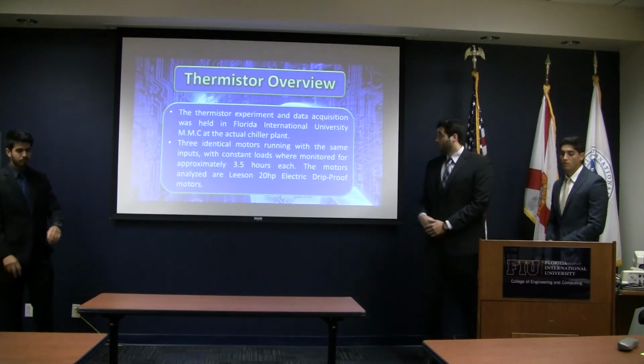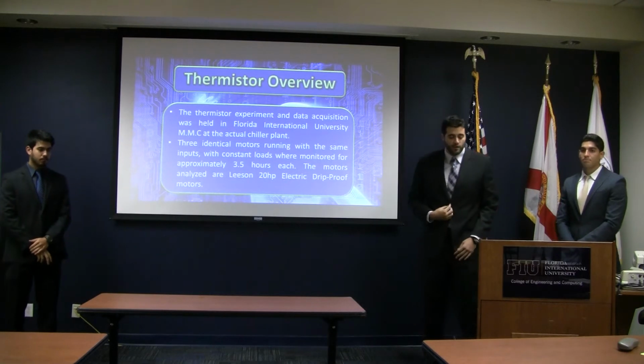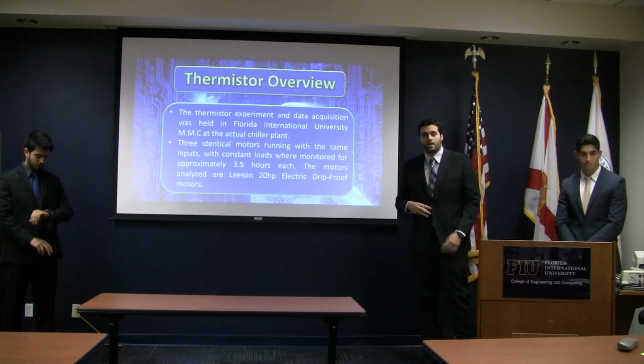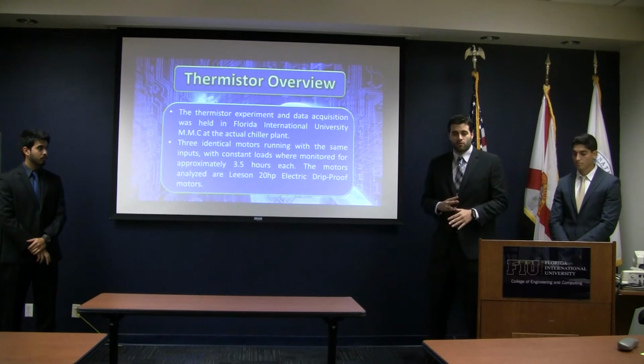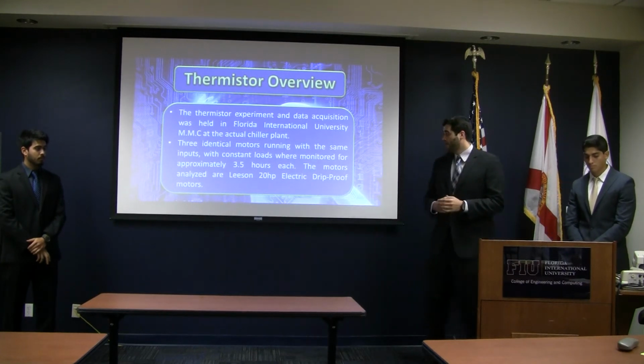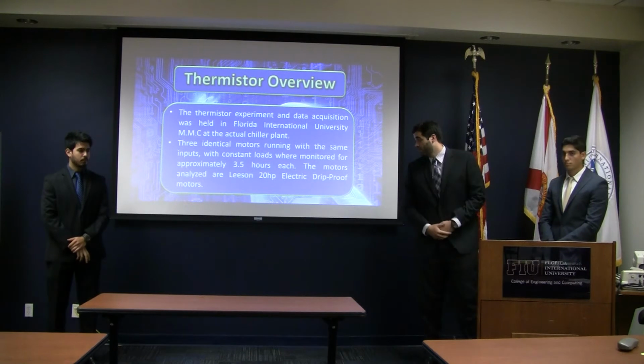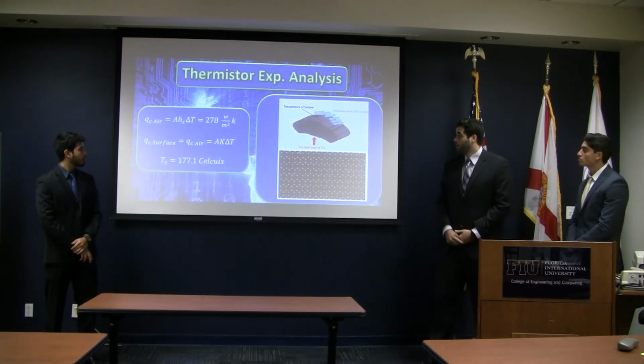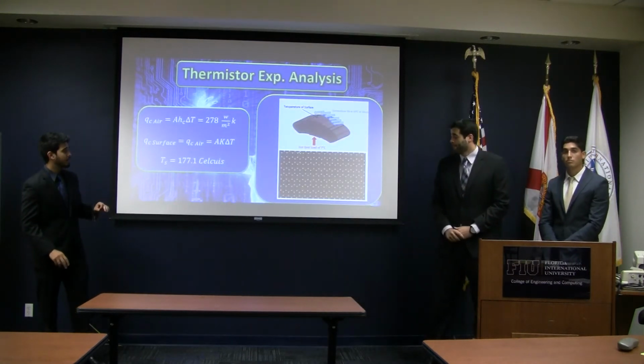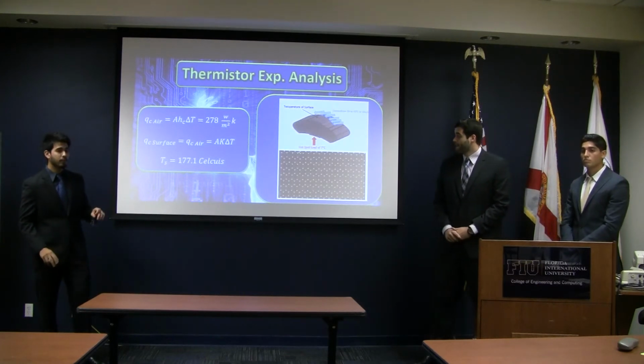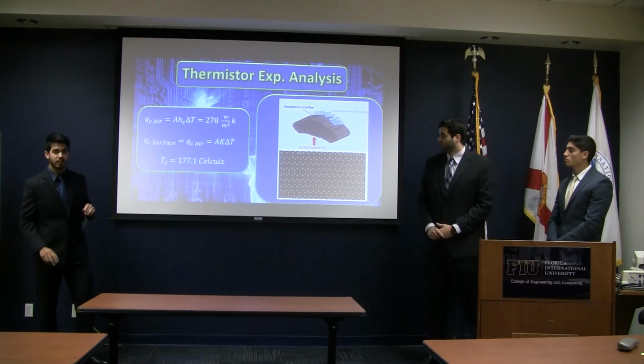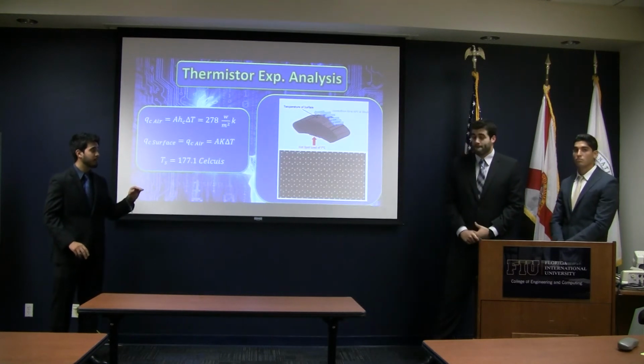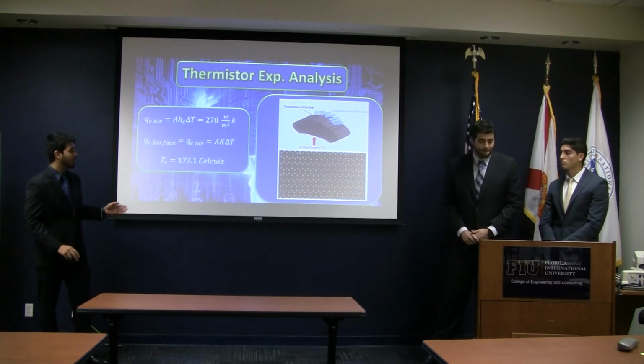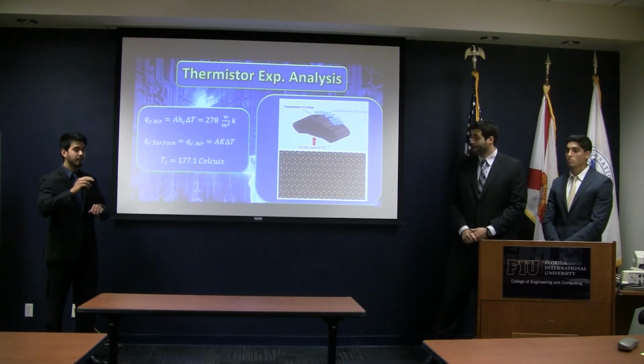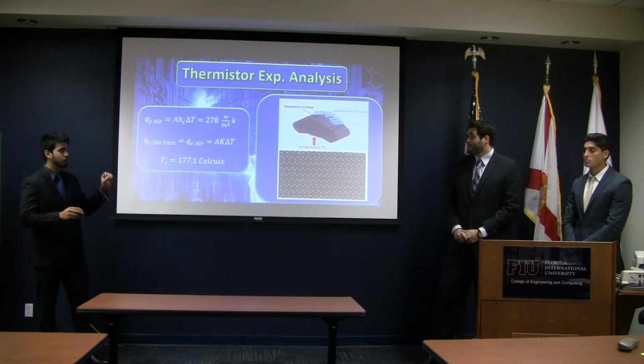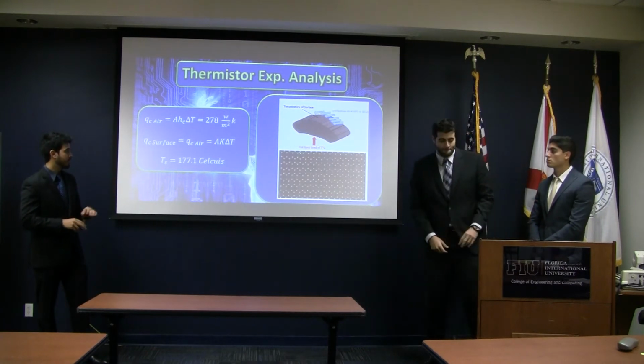So our thermistor experiment was done by going to the FIU chiller plant, having three of the same motors with the same loads and same input values, and installing the system and having it run for 3.5 hours. First we had to do a little bit of analysis into the calibration of the temperature. Since we were going to monitor the exposed winding at the surface, and the hotter temperature is located inside, we wanted to see if we could calculate the difference in temperature between them. That way we could get the true heated temperature reading.